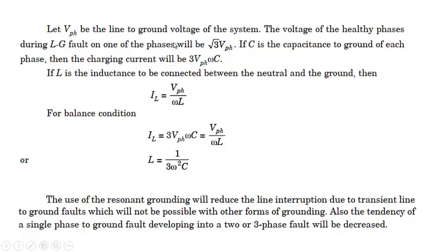Let V phase be the line to ground voltage of the system. The voltage of the healthy phase during the ground fault will be √3 V phase. If C is the capacitance to ground of each phase, then the charging current will be 3 times V phase omega C. That we have already seen, that it will be equal to 3 times IC. So in terms of phase voltage and omega C, it will be like this.